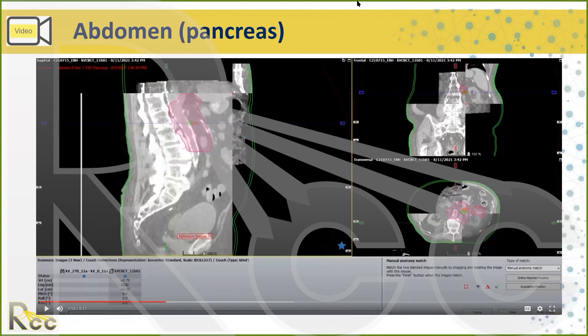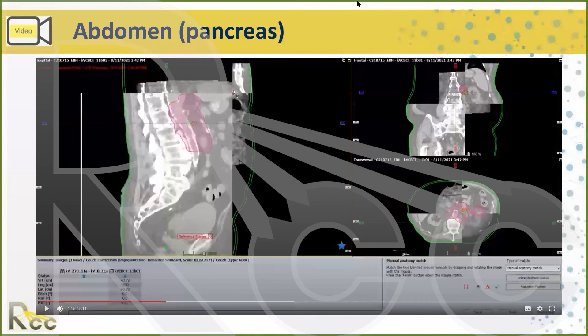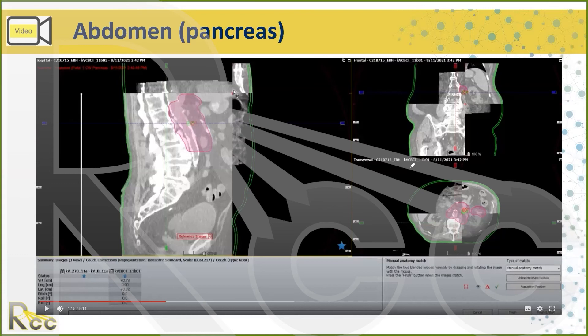There's a question: what is the slice thickness of the cone beam CT and how do you match it with the slice thickness of the planning CT? The cone beam slice thickness is different — it depends on the machine. As a user, you should know that when comparing on the axial or transverse view, you're looking at a volume, not exactly a slice. It might be a volume of one millimeter for radiosurgery, or it might be two to three millimeters.